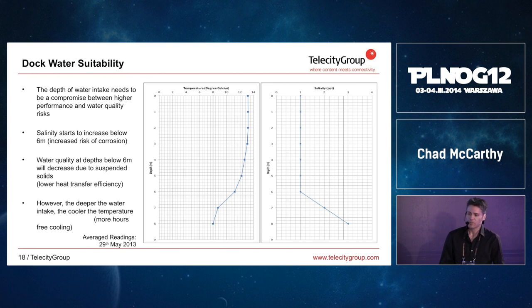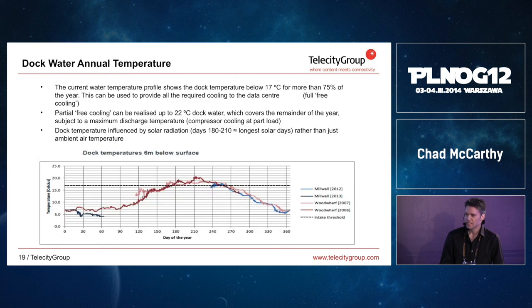And the reason the temperature is so critical, of course, is because we're focusing on free cooling. This one is particularly relevant. The diagram on this page addresses the variance in temperature over the year. So during the summer period, you can see that the temperature of the water comes up to around 20 degrees, which is a higher temperature than you would strictly use for free cooling. We're designing the system so that we can have full free cooling at or below a dock water temperature of 17 degrees C. So the chilled water temperature inside the data center itself is 19 degrees. And this diagram shows that for more than 75% of the year, this is the case. So for 75% of the year, we can have full free cooling in the data center using the dock water.